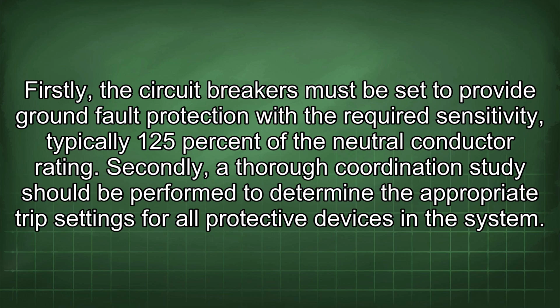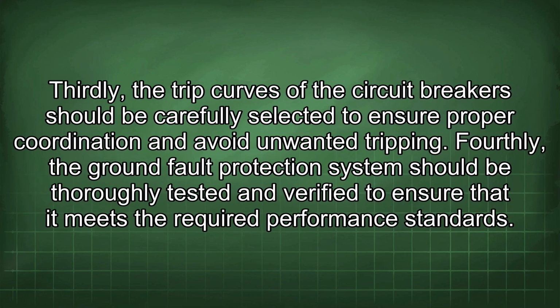Firstly, the circuit breakers must be set to provide ground fault protection with the required sensitivity, typically 125% of the neutral conductor rating. Secondly, a thorough coordination study should be performed to determine the appropriate trip settings for all protective devices in the system. Thirdly, the trip curves of the circuit breakers should be carefully selected to ensure proper coordination and avoid unwanted tripping. Fourthly, the ground fault protection system should be thoroughly tested and verified to ensure that it meets the required performance standards.